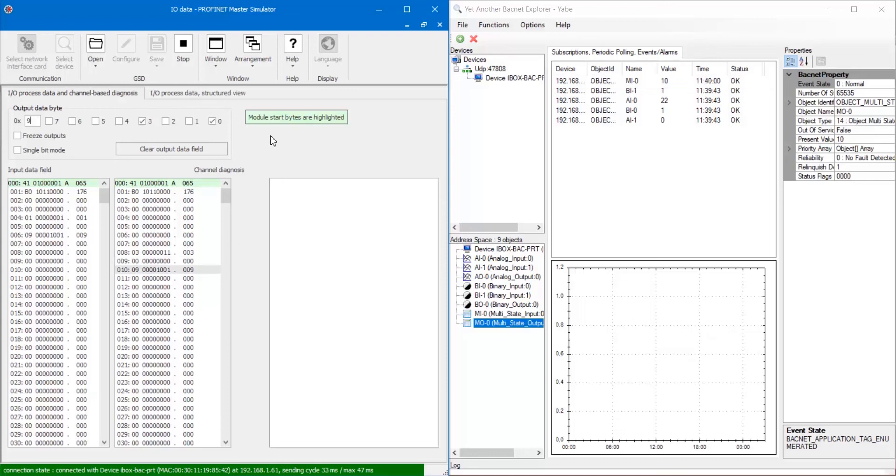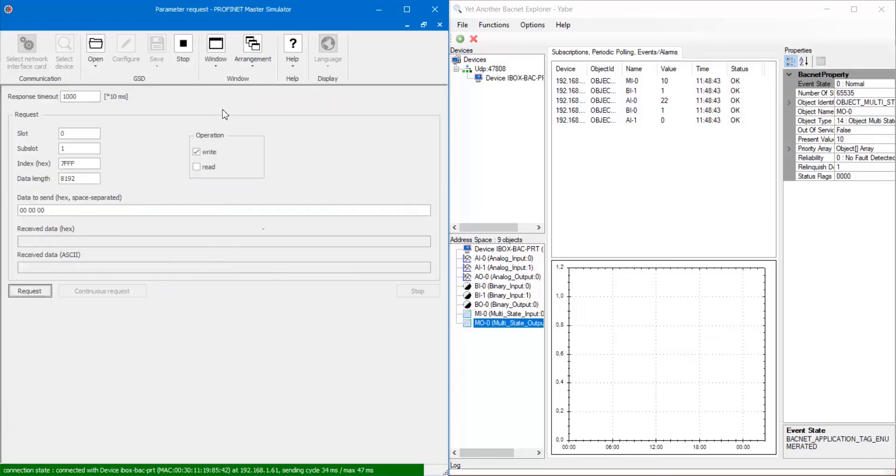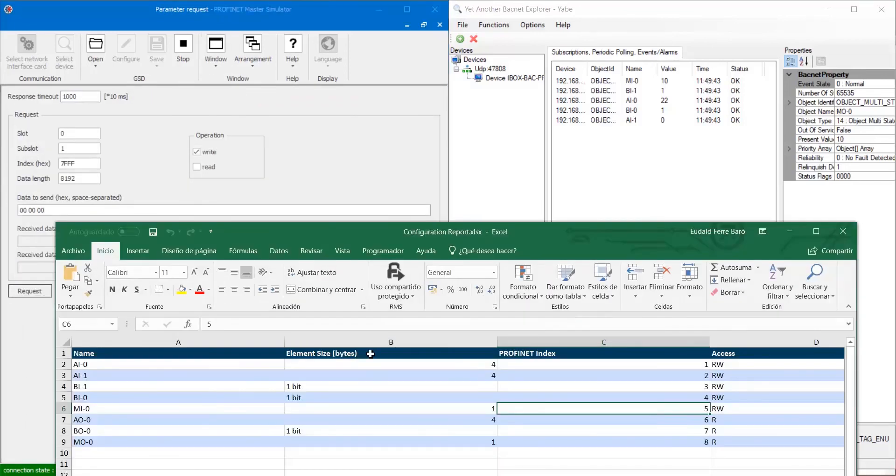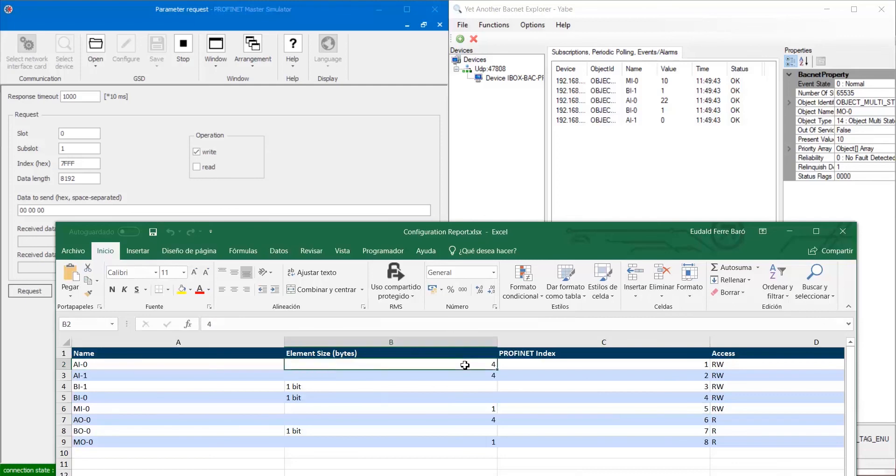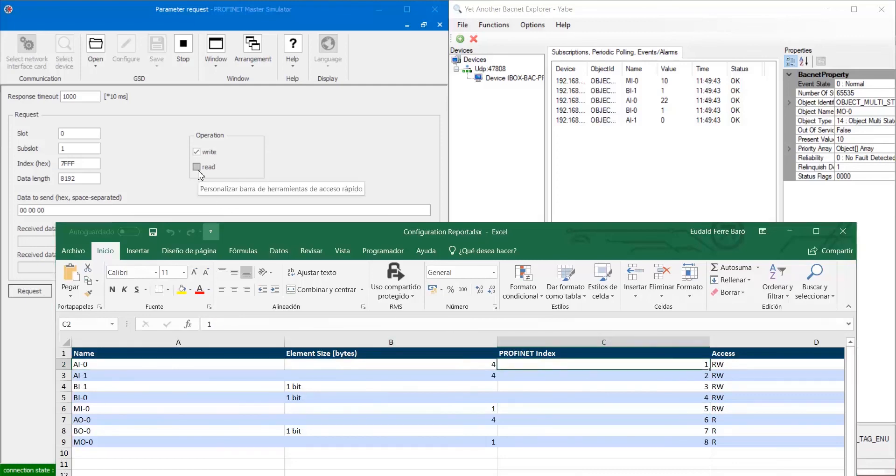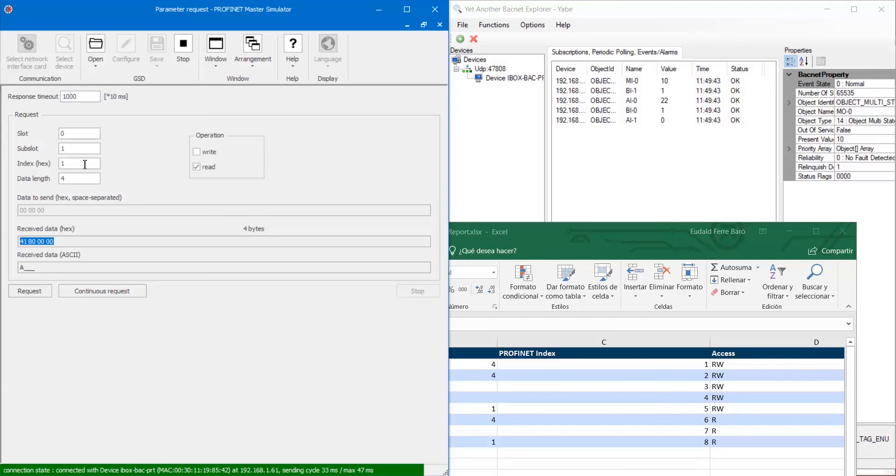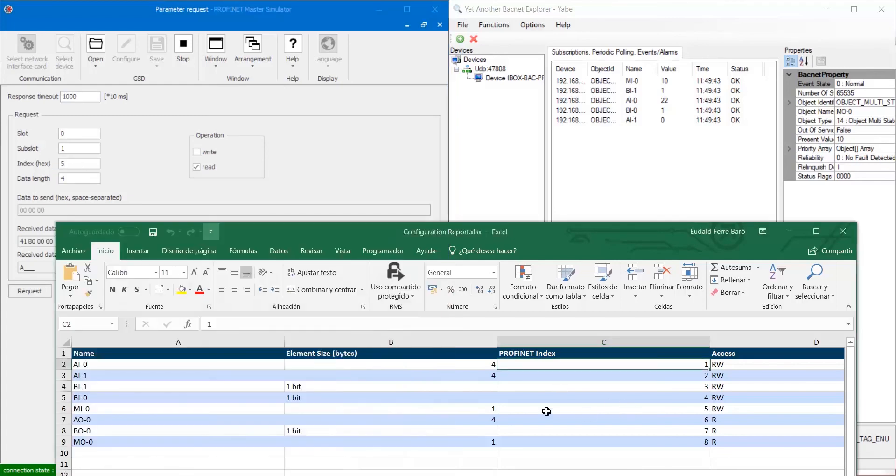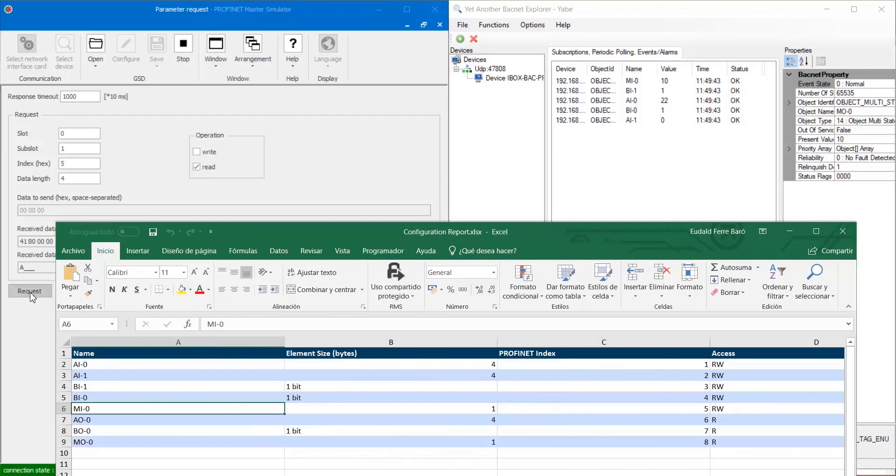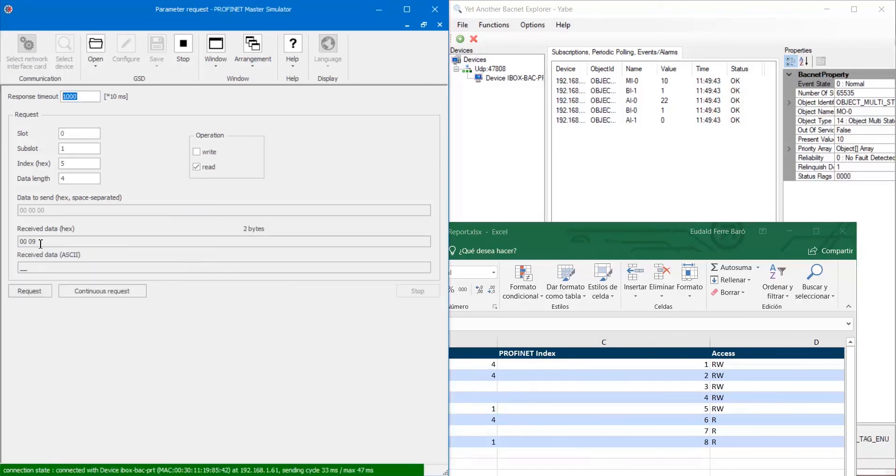Finally, we are going to test acyclic data. To do so, open parameter window and check Profinet indexes on the configuration report. The first signal we are going to read is AI0 and the Profinet index is 1. So, set index and data length in the request parameters and finally click on request. Then, we will do the same with signal MI0.